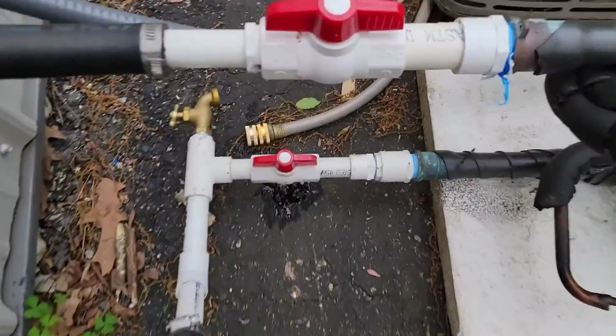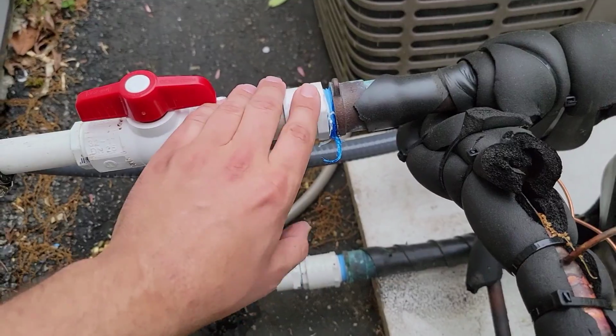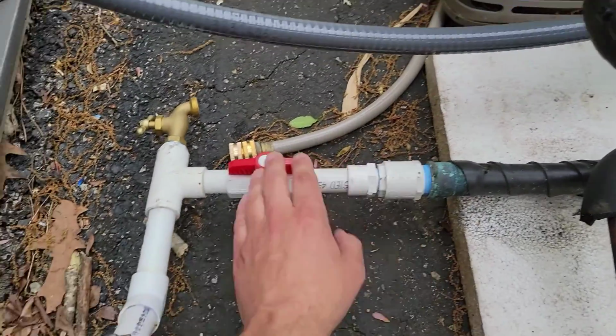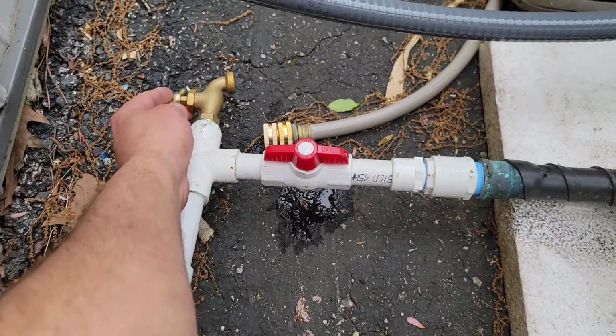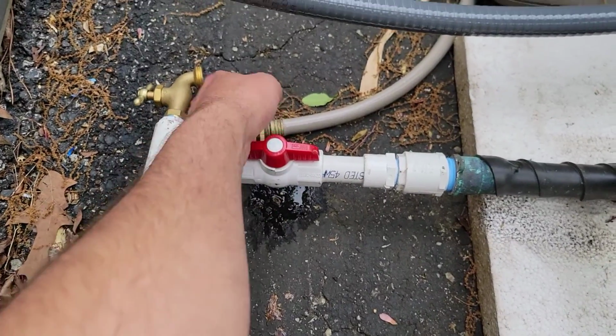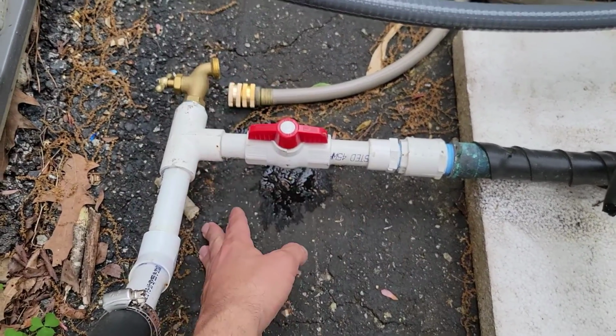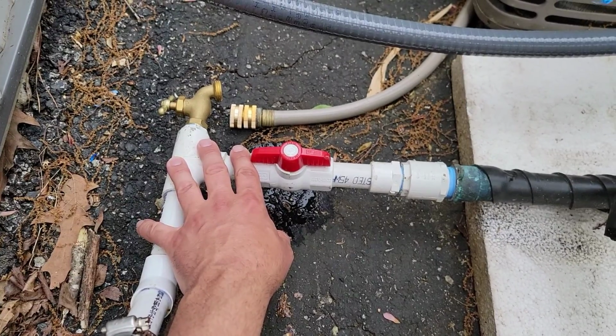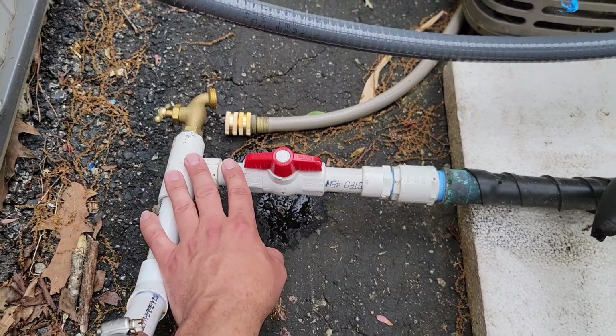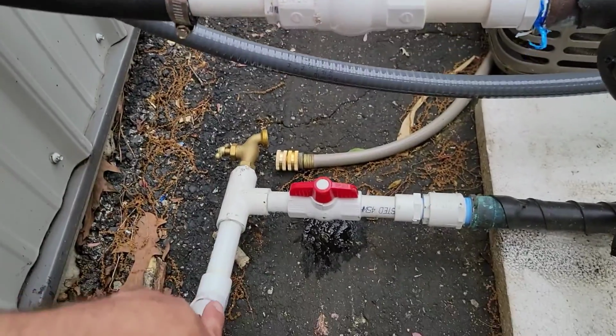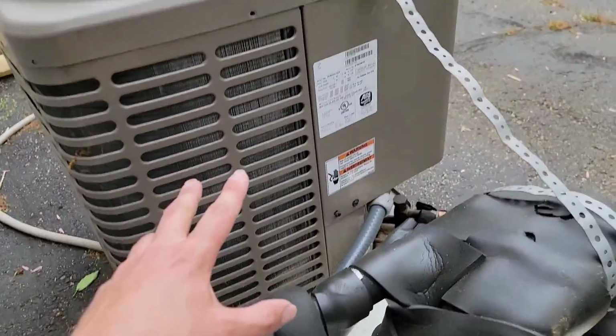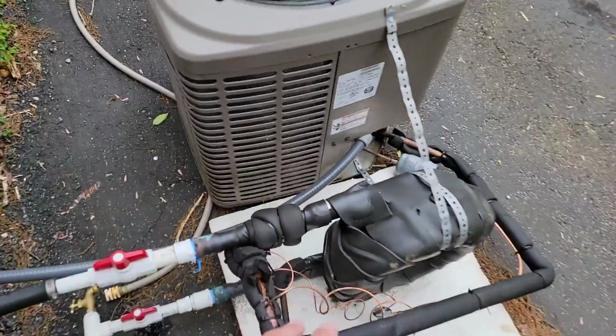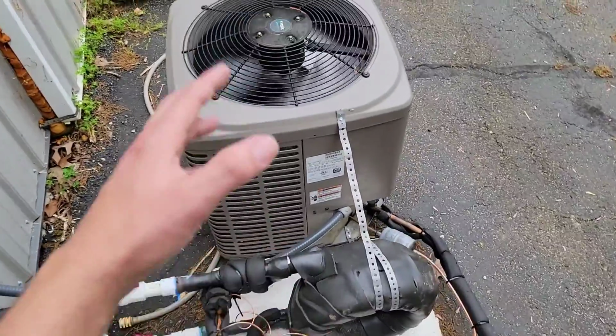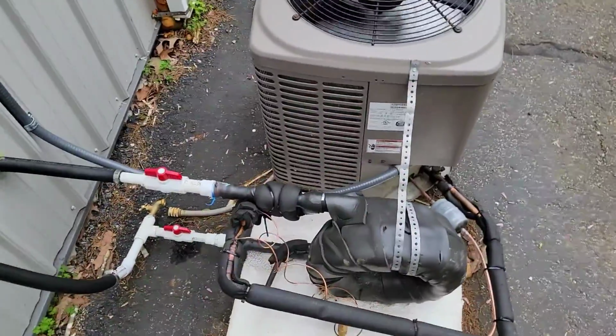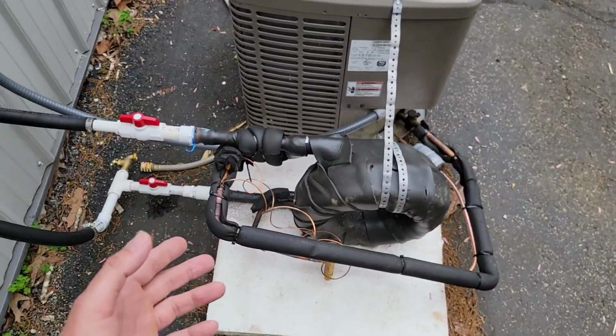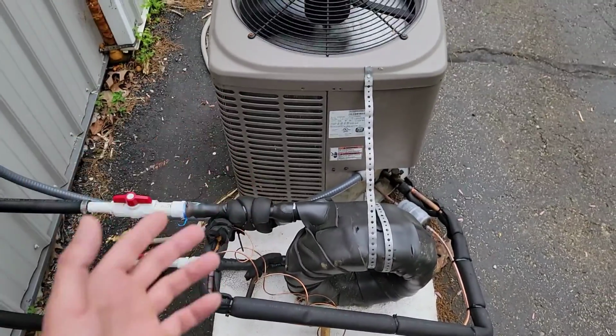Now, this is the inlet and outlet pipes, the return and supply. This right here is a little valve that I put, a little spigot, a little hookup so that I can add water and so that I can check pressure. I'm going to show you how I check pressure on this. And the reason you want to check pressure is because these things matter to you. Just like checking the refrigeration's pressure to make sure that I have a good suction and discharge, just to make sure that I'm not affecting my compressor. I have high head pressure or I have low suction to where I'm freezing up. I want to make sure that I check everything.